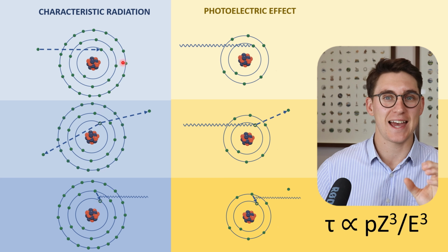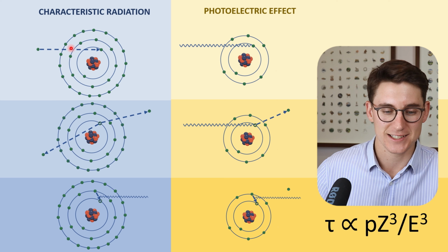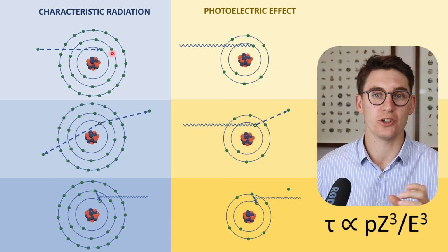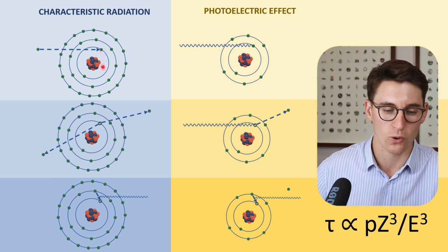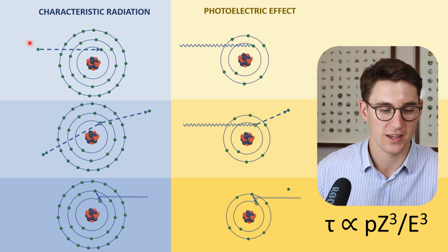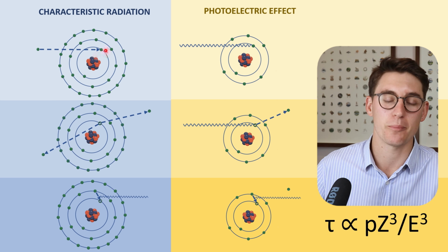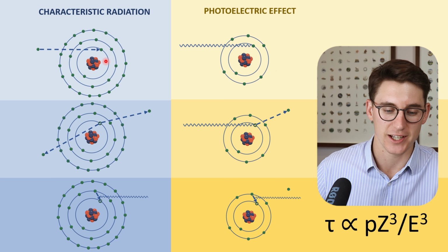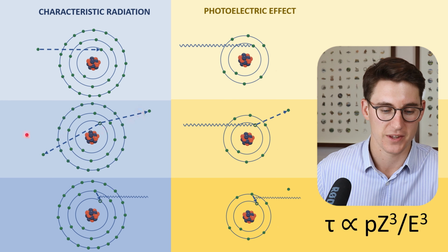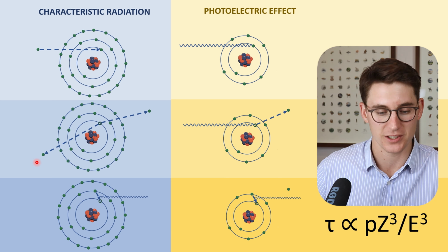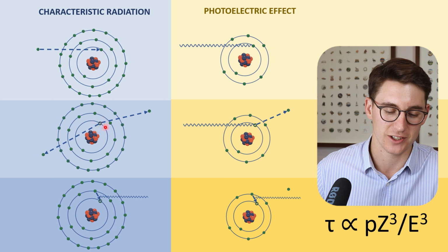Now, this is occurring at the anode within our X-ray tube. We have an electron here that is accelerating towards our anode. Now we know our anode is made of tungsten, a large atom here, 74 protons within the nucleus. If the energy of this bombarding electron is higher than the binding energy of this K-shell electron, that K-shell electron will then be released from the tungsten atom, as well as our incident electron being deflected away. We've now created a space within our K-shell here.